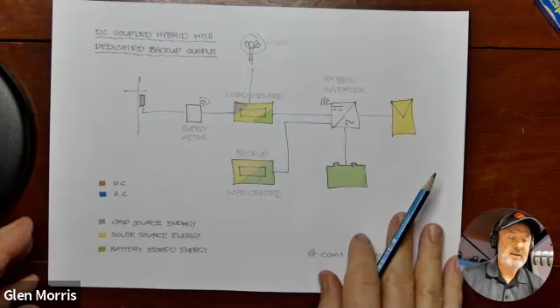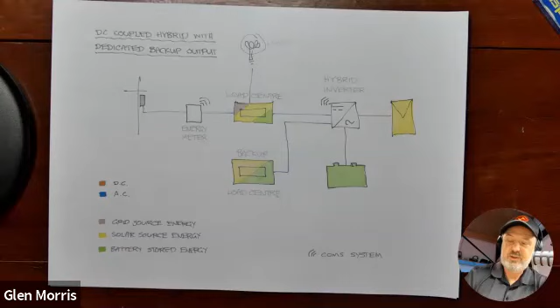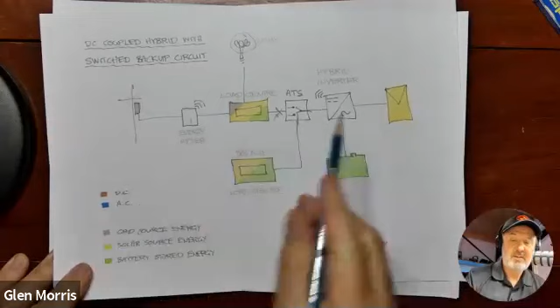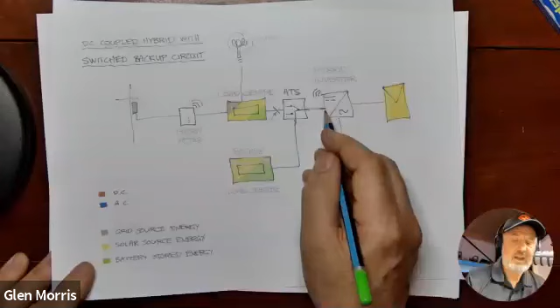One more, and I think this is, I've got two more. So this one's very similar. Just to flash them back again, this one here, I've got an ATS. That means I've only got one port on this inverter, one AC port, and it can actually change its mode of operation from grid feeding to standalone. It does that change of mode whenever the grid's lost and this automatic transfer switch operates.